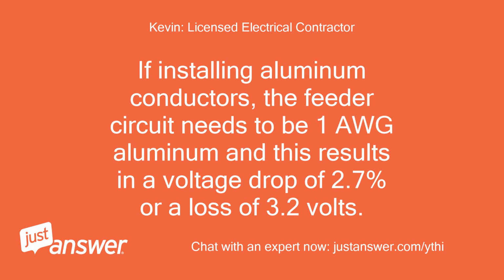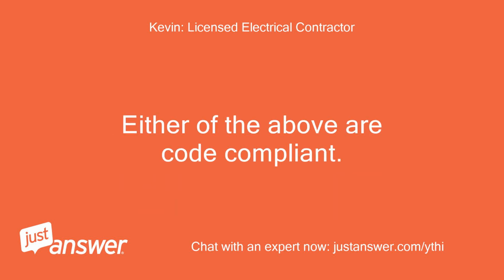If installing aluminum conductors, the feeder circuit needs to be 1 AWG aluminum, and this results in a voltage drop of 2.7% or a loss of 3.2 volts. Either of the above are code compliant.